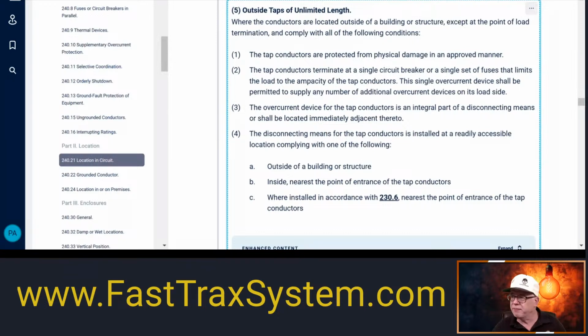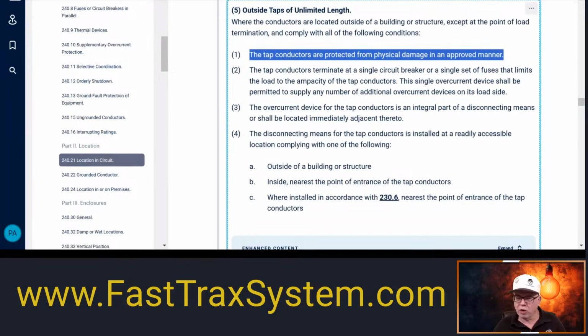Because there's only certain things that qualify as protection from physical damage, like Schedule 80 PVC, rigid, intermediate, things like that. EMT now is designed to protect from physical damage. It wasn't a couple cycles ago, but it is okay now. So that's the first thing. Work with your AHJ. If you put it in rigid or intermediate or Schedule 80 PVC, then you ain't got to worry about an argument.